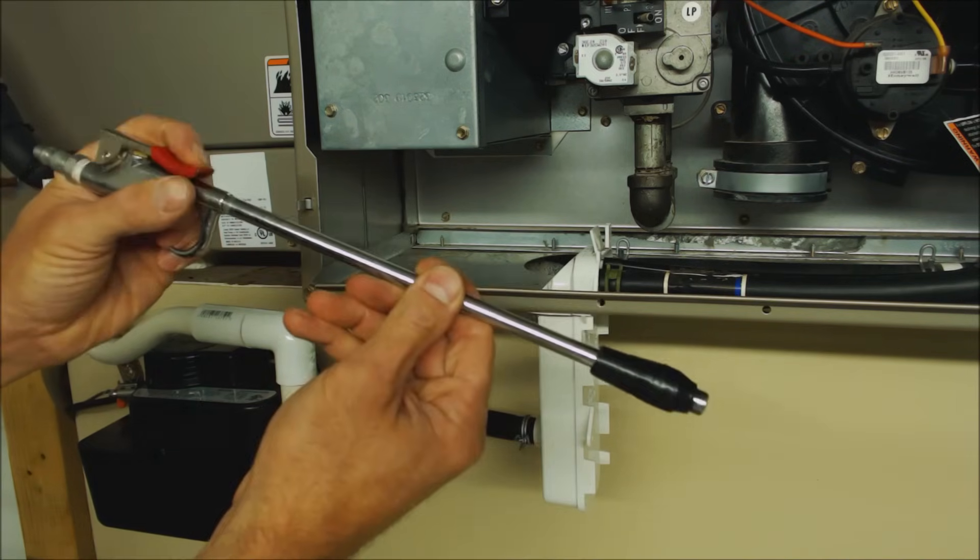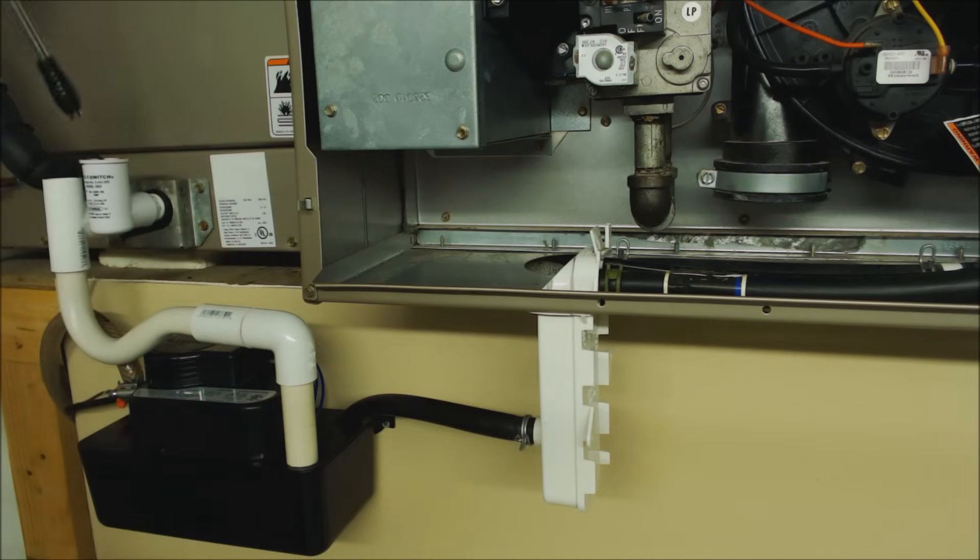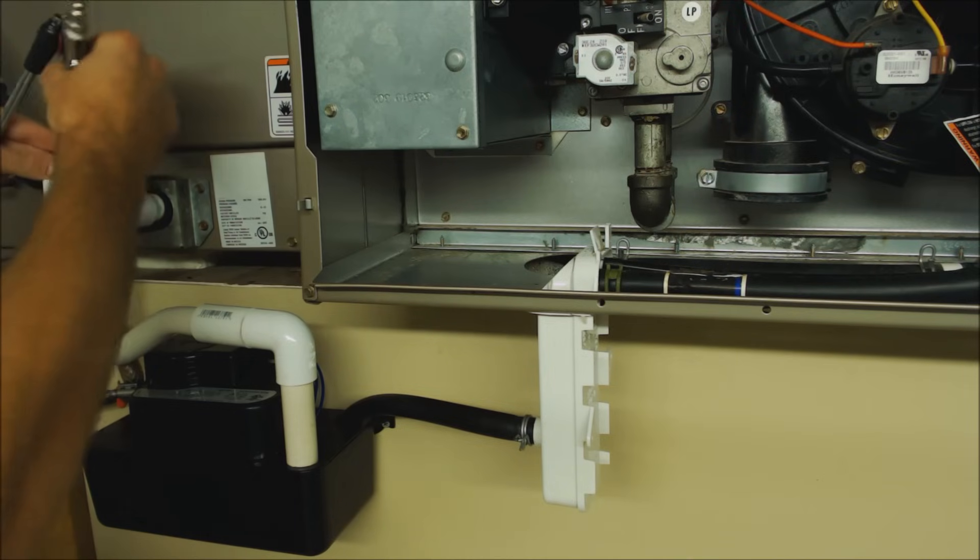Another way to do it is with compressed air, and on this one I have electrical tape right there. When we push this right down in there you want to get past this part of the T. You want to get down into the trap. If you don't have an extension piece like this you could just use a piece of 3/8 copper like this and the same thing.